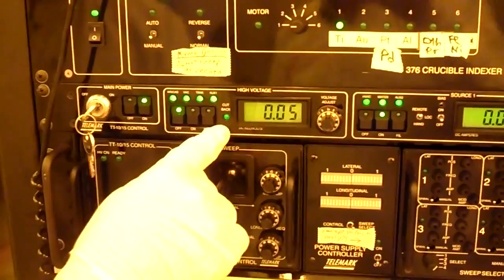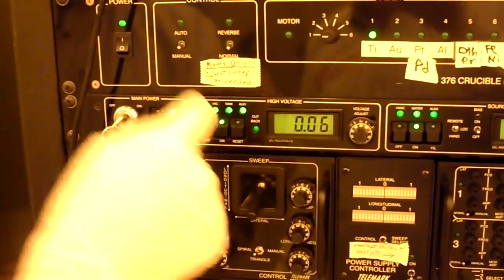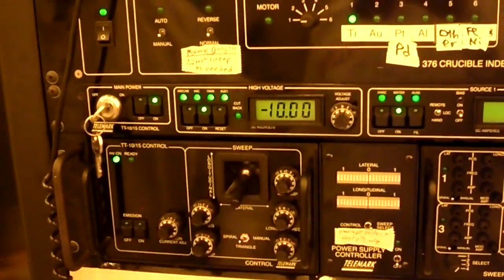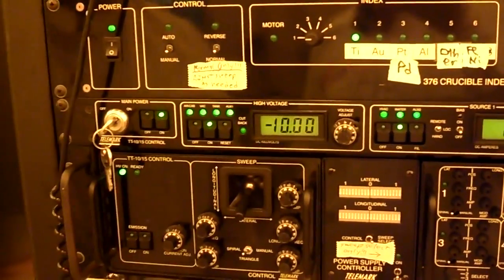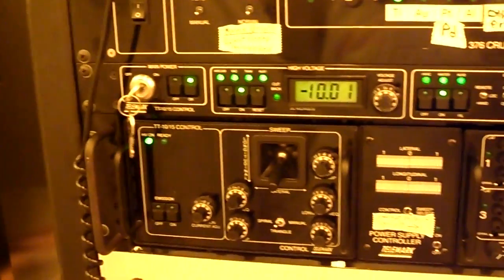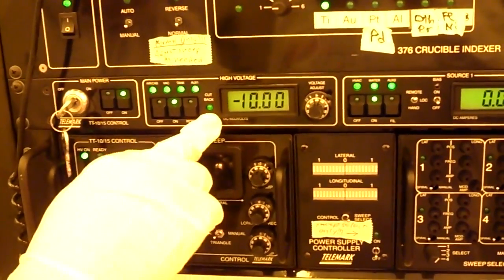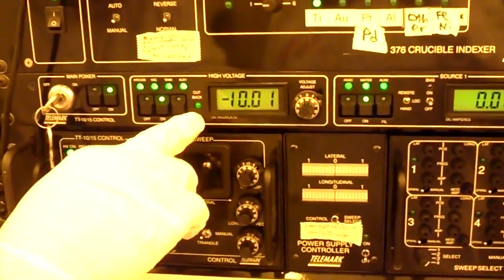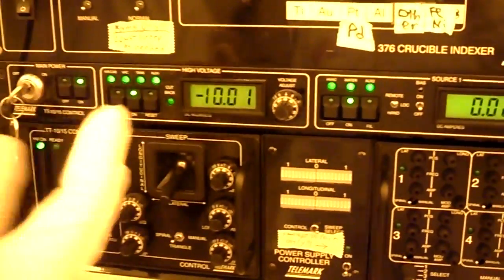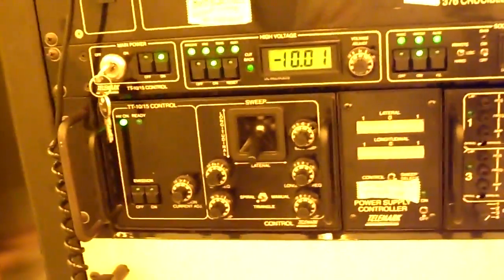All right, and then it defaults to the off position. Press on, and you'll see we're now at minus 10 kilovolts, and it'll say high voltage on here. And remember this cutback light? You can see it's not completely off, but it's not completely on. It's sort of partially lit.